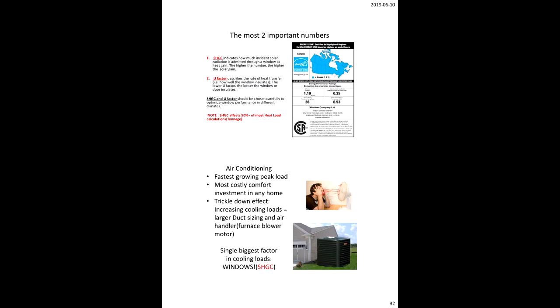This is a little study that was done, a new design manual by the NRC. It would be really useful for you folks to have a look at. It's going to be available within the next month, called Mechanical Design for Low Load Housing. It identifies things like if you have a solar heat gain of 0.3, called mid-range, versus higher than 0.61, you can increase your tonnage by a half ton to a full ton just on a townhome.